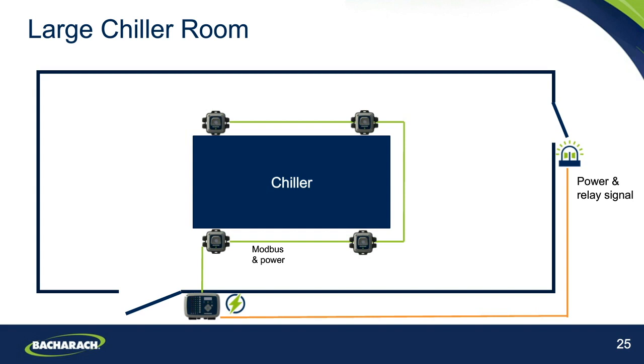But if we look at this room here with two entrances, we can see that with the gas detectors within the space, we have those audible and visual alarms. And we can power and communicate to those just with a single controller outside of one of the entrances, which again is able to provide that audio-visual alarm requirement. But from there, of course, we can drive power and a relay signal to an additional horn strobe outside another entrance. So we can very easily here have a system that is centralized and controlled from one place, rather than having to have multiple systems giving you difficulty in terms of driving the collection of audible and visual alarms.